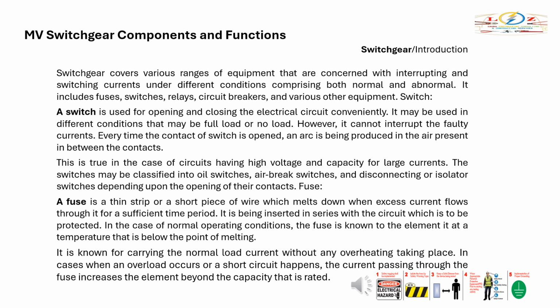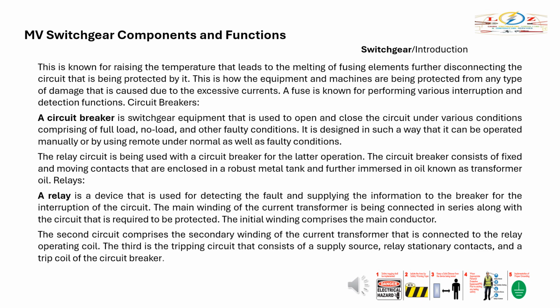It carries the normal load current without any overheating taking place. When an overload or a short circuit occurs, the current passing through the fuse element increases beyond the rated capacity. This raises the temperature, which leads to the melting of the fusing element, further disconnecting the circuit that is being protected by it. This is how equipment and machines are protected from damage caused by excessive currents. A fuse performs various interruption and detection functions.